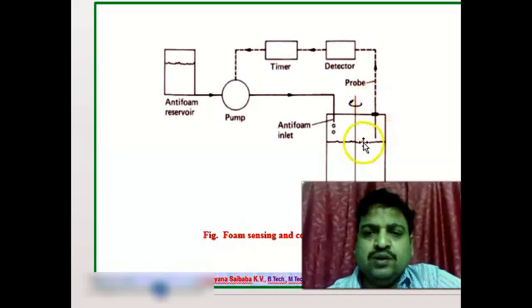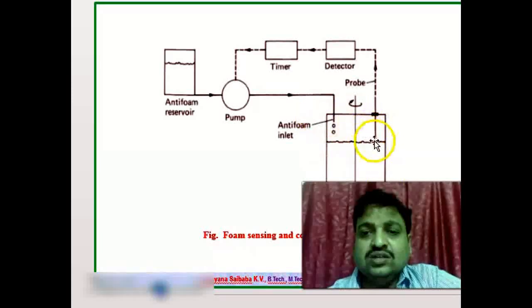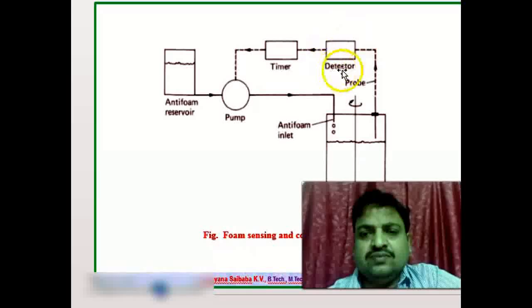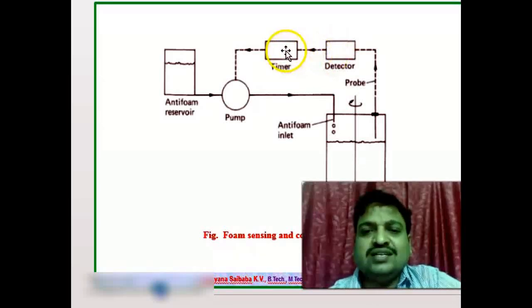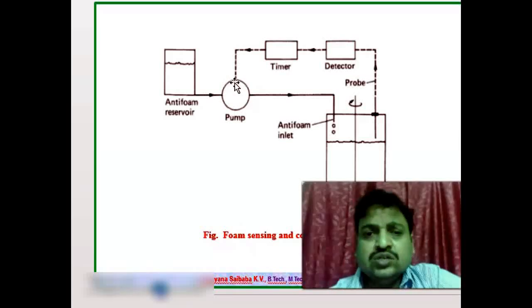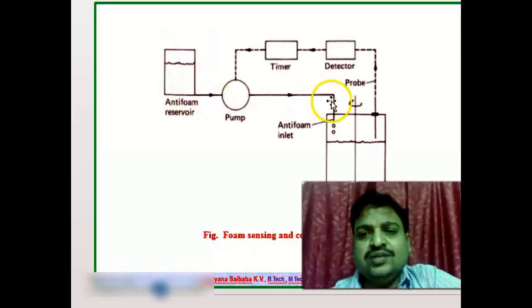When the foam touches the probe, it acts as an electrolyte and completes the electrical circuit with the vessel acting as earth. The resulting current signal is detected by the controller, which immediately activates the timer and the final control element — a valve or pump. The pump then delivers anti-foaming agents from the reservoir into the fermentation process.